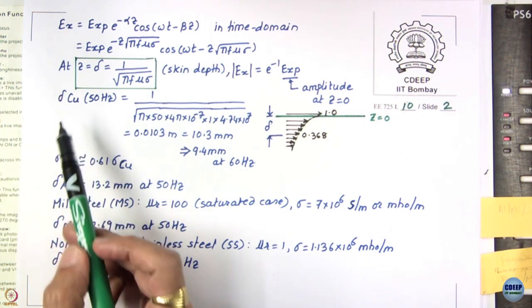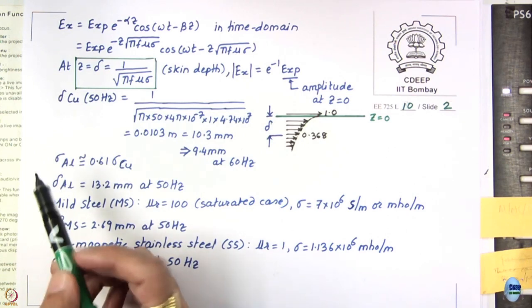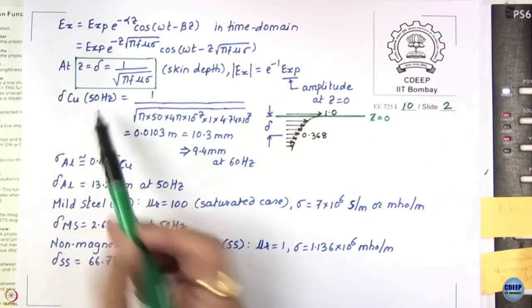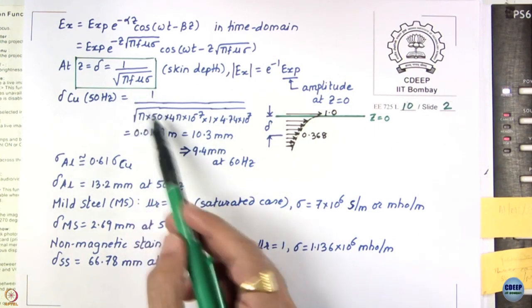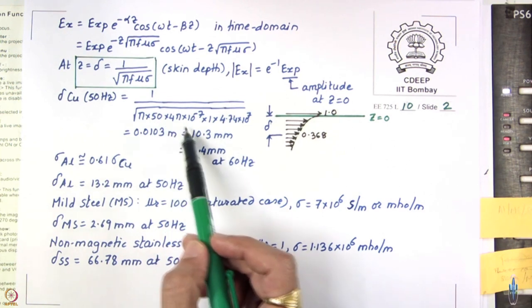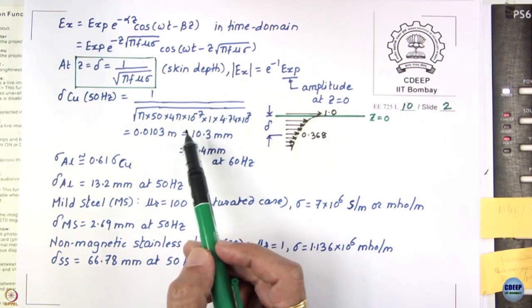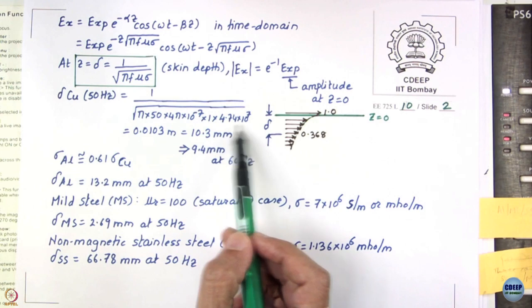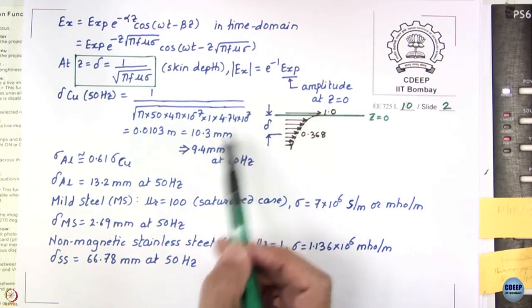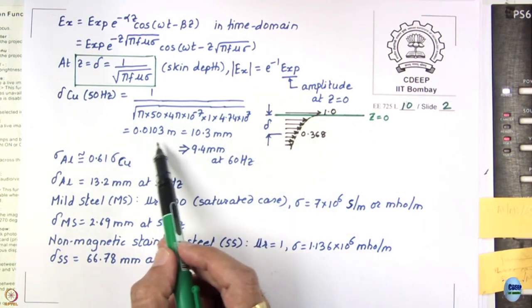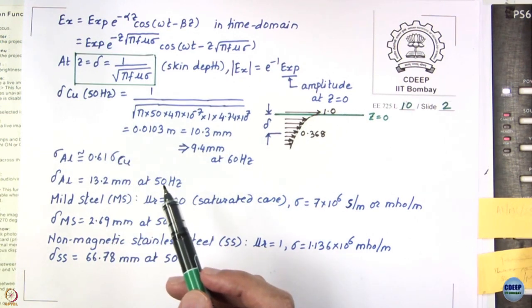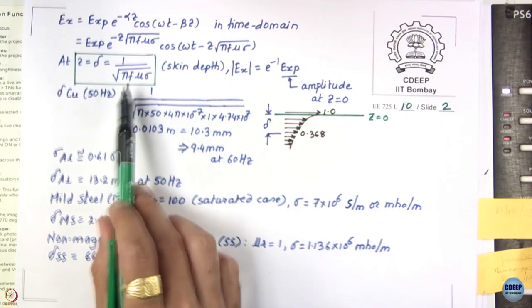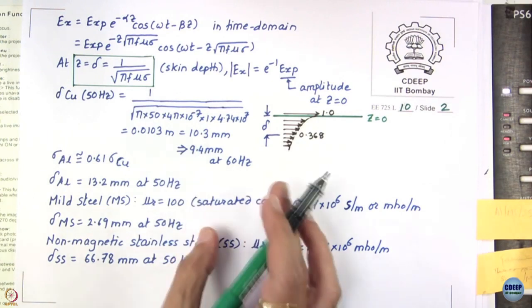Calculating skin depth for materials commonly used in electrical machines: for copper at 50 Hz, mu_r is approximately 1 (diamagnetic) and conductivity is 4.7×10⁷ S/m, giving a skin depth of 10.3 mm. At 60 Hz it is 9.4 mm, since skin depth is inversely proportional to the square root of frequency — as frequency goes up, skin depth drops. For aluminum, conductivity is 61% of copper's, giving a skin depth of 13.2 mm at 50 Hz.